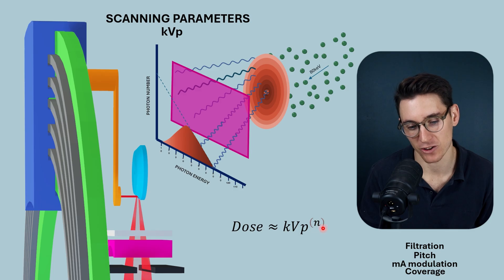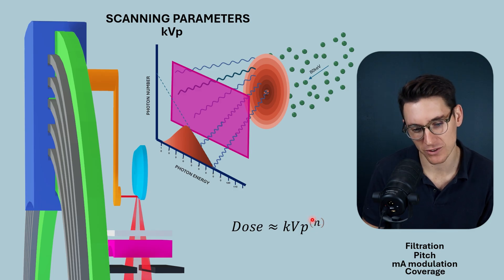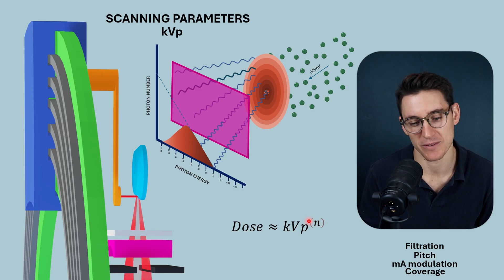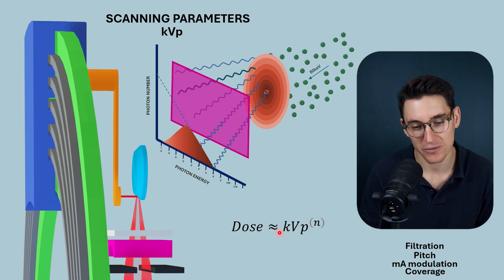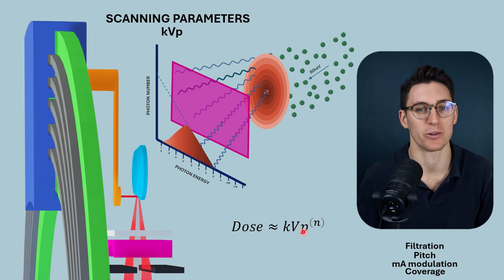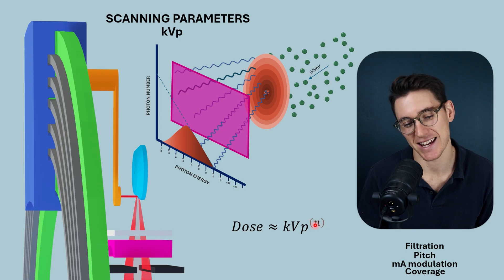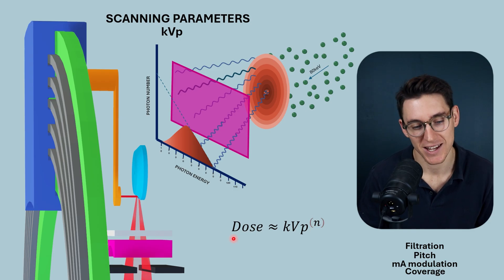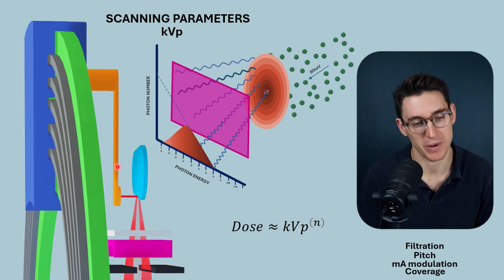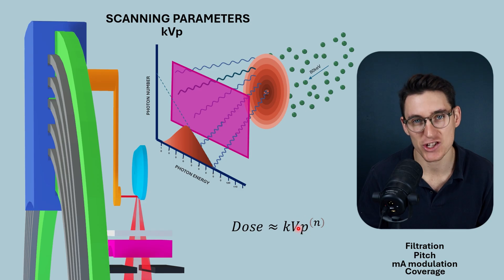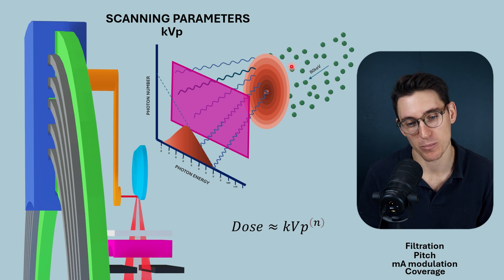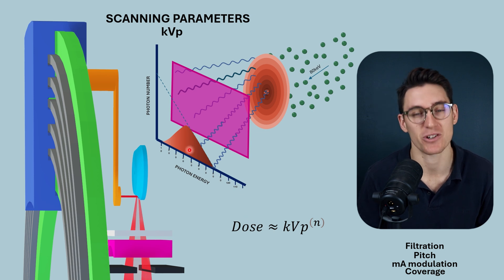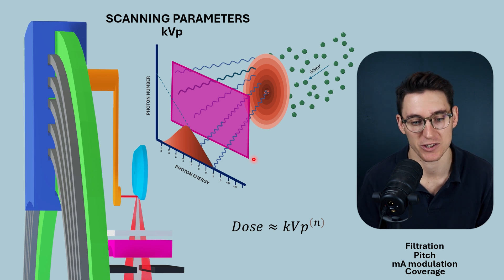Dose is roughly proportional to KVP to the power of n. In traditional radiography, we often say dose is roughly proportional to KVP squared. In CT scanners, n is normally closer to about 2.5 or 2.6, depending on the filtration and the type of CT scanner used. Minor changes in KVP are going to have quite drastic changes in the dose to the patient, predominantly due to the number of x-ray photons heading towards the patient.